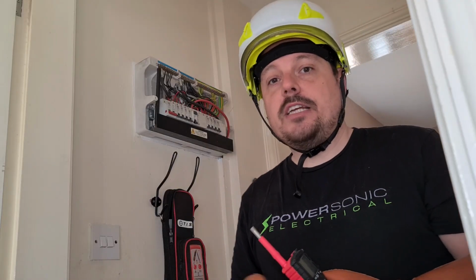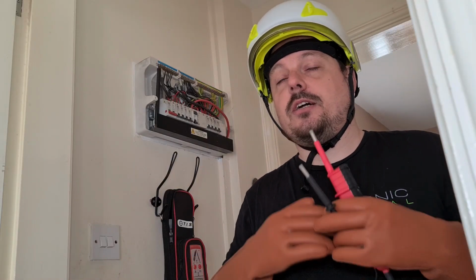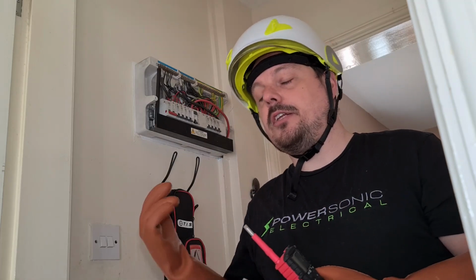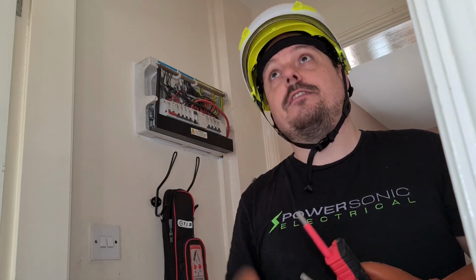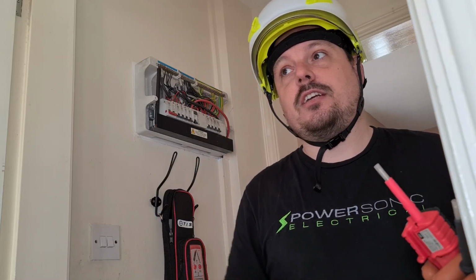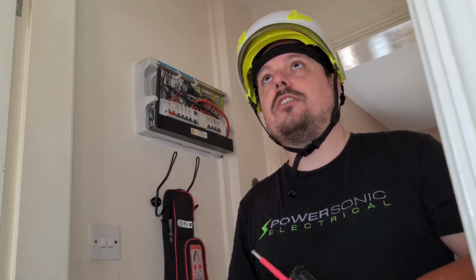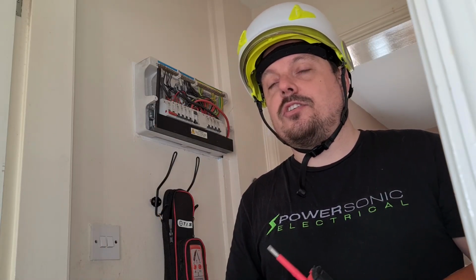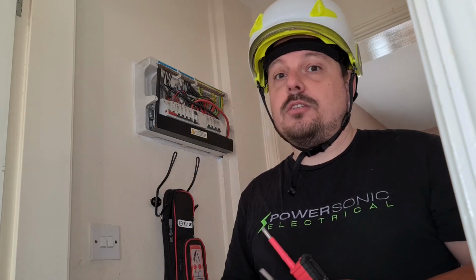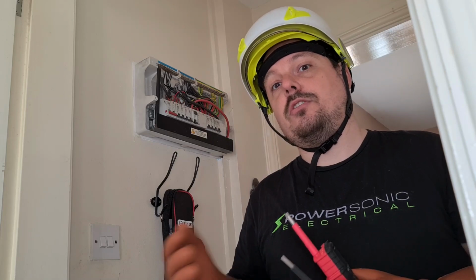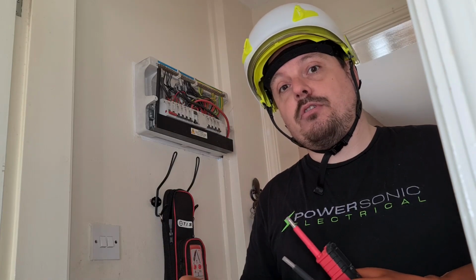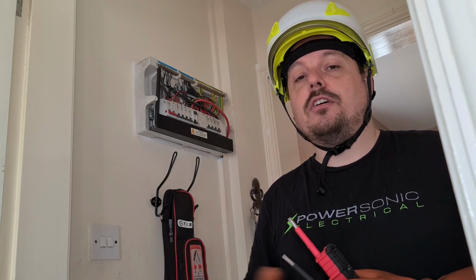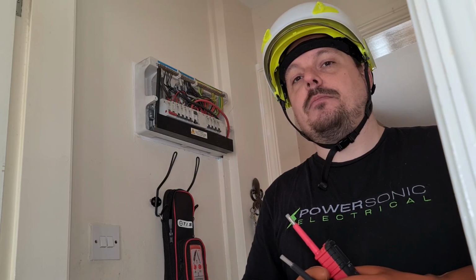Okay, so we know with reasonable confidence that this installation is now off and isolated. The main switch outside is locked off. I've seen functionally it doesn't operate, none of the sockets have power to them, nothing's currently on, the lighting's not working and such. But if you're going inside an enclosure before you've verified that it's dead and safe to work, you should always assume that it could be live and take appropriate measures with your PPE just to cover in that case. And yeah, this would be considered by some as being over the top.